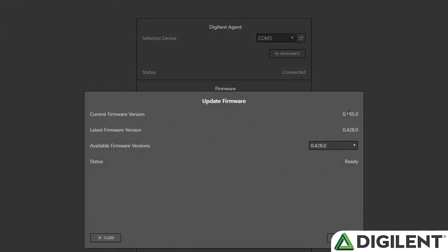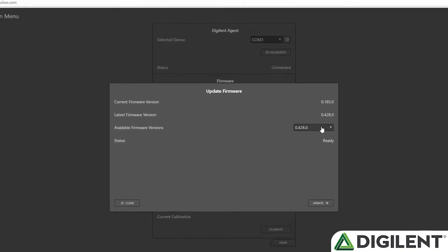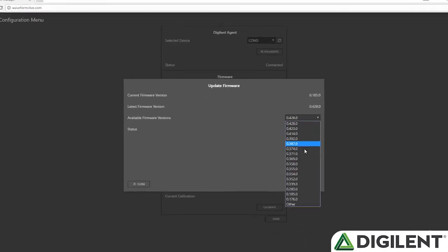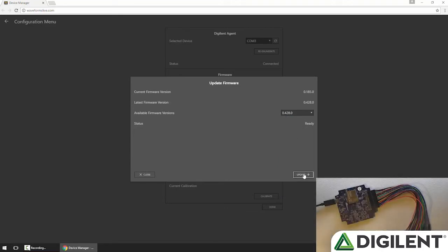Again this shows the current version of the firmware, the latest version that's available on the servers, and lets me choose a version to update to. So I'll update to the latest 0.428.0, and click Update.